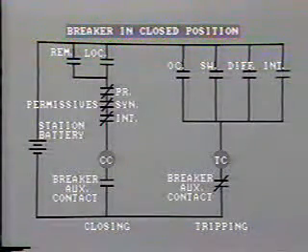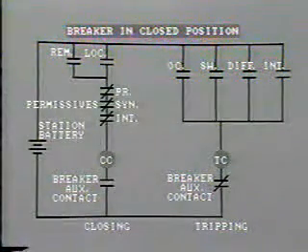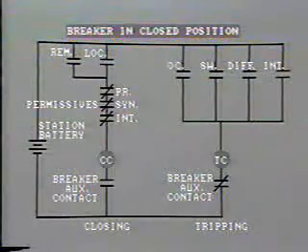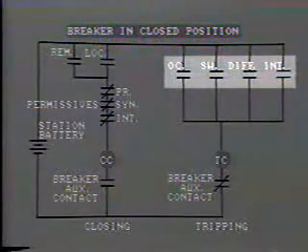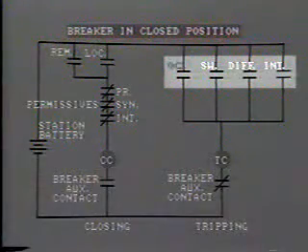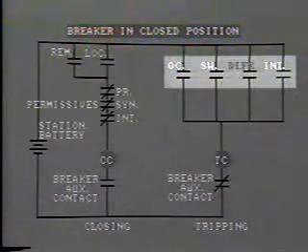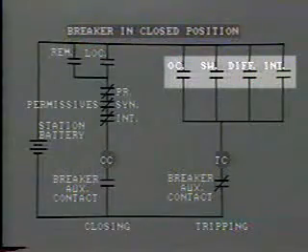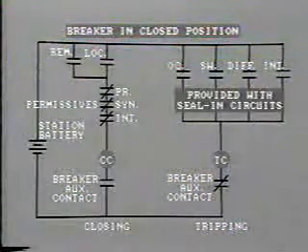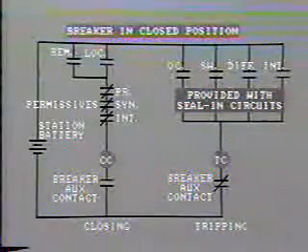To trip the breaker open, the tripping circuit must be energized. In the case of a tripping circuit, instead of permissive contacts in series, we'll find several pairs of contacts in parallel. Look at these tripping contacts: overcurrent relay, manual switching, differential relay, remote inter-trip. Closing any one of these pairs will energize the tripping circuit and open the circuit breaker. Often these tripping contacts are provided with seal-in circuits, as discussed in the previous segment.